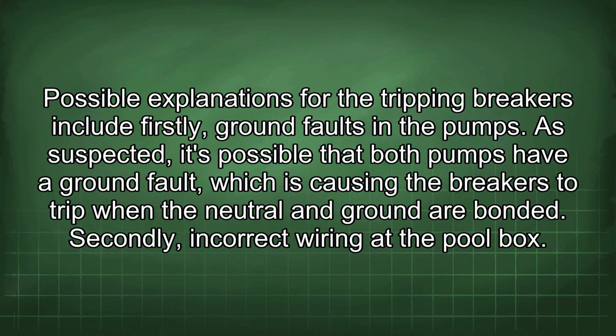Possible explanations for the tripping breakers include, firstly, ground faults in the pumps. As suspected, it's possible that both pumps have a ground fault, which is causing the breakers to trip when the neutral and ground are bonded. Secondly, incorrect wiring at the pool box.